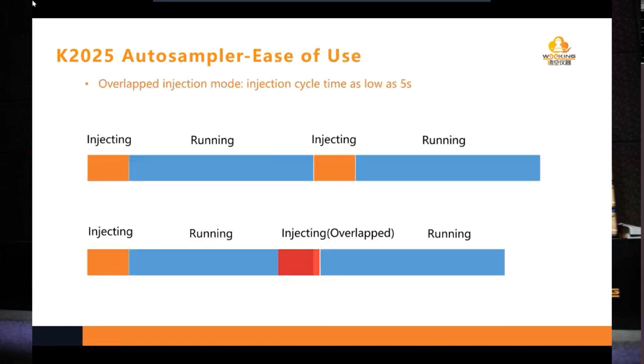The autosampler has an overlap injection mode for shorter injection cycle time, especially when the sequence run is performed. The normal mode is injecting, running of sample, and after the sample is finished, the next injecting action starts and the next running. When the overlap mode is used, the second injecting action can be performed before the last run is finished. So the run should be finished at this time, but the injecting action starts from this time. So the next run can be started in a very short time. We use this time for the next run.